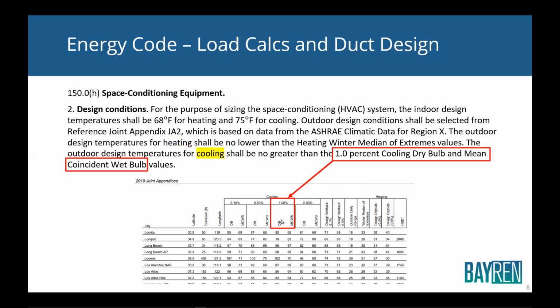As I mentioned, the cooling temperature is what's called the 1 percentile. There's a dry bulb temperature, and then there's something called the mean coincident wet bulb. California has 16 distinct climate zones. We have places like Truckee, California by Lake Tahoe, that the design temperatures are comparable to a lot of places in Alaska. And then we have Death Valley and Palm Springs and Palm Desert, which are some of the hottest design temperatures in the country, hotter than a lot of places in Arizona, if not the hottest in the country. So we have a real variety.